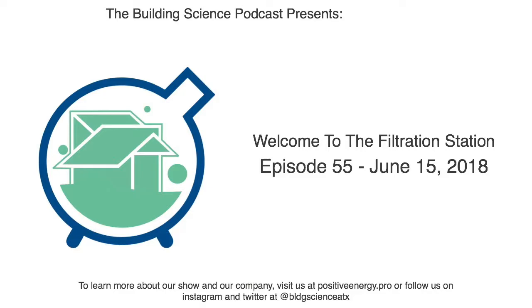All right, so that was electrostatic attraction, and I pulled you away. What's the last way that particles would be leaving an airstream? Another method is sedimentation. As the particle goes through the filter, it just slows down and gets stuck in the filter. Those will be bigger particles, the coarse particles you talked about in the beginning. When you see dust in the sunlight, the big particles are settling to the floor. Those are the big ones, and that could be an example of sedimentation. Yep, the dust, exactly. The dust falling out. And just to touch on that, and then we'll talk about MERV.